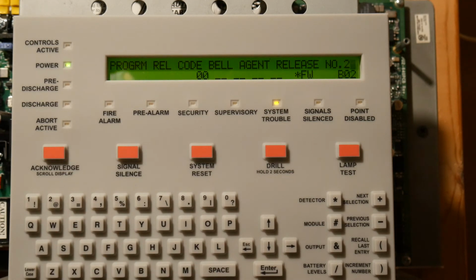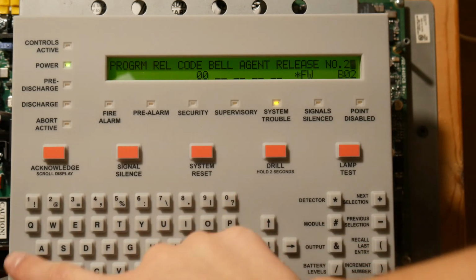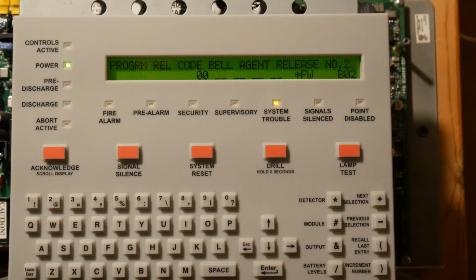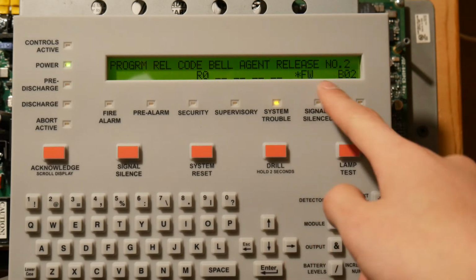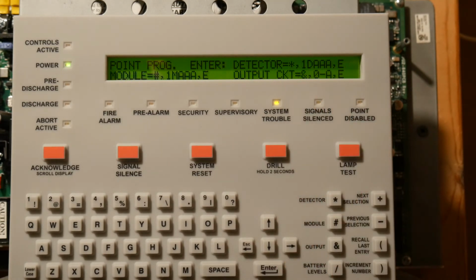Okay. So the way you add dots and stuff is you press your shift key, which is this one, and you press number 2. And now we're going to scroll to zones. Also, I'm sorry that beeps. I'll show you how to turn off the beeping in a second. We're going to press R0 since it's a releasing zone and we want it as releasing zone 0. Everything else is fine, so we're going to press Enter. Now we programmed our NAC and usually everything is fine.